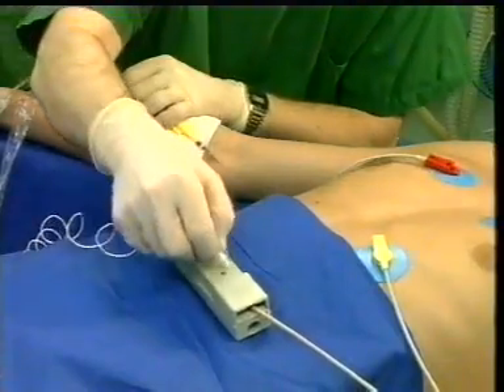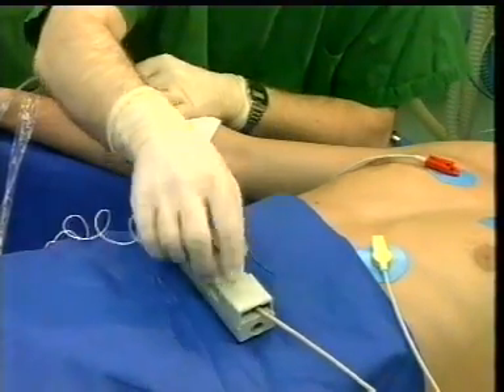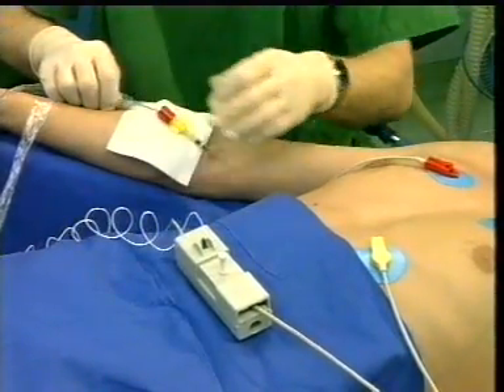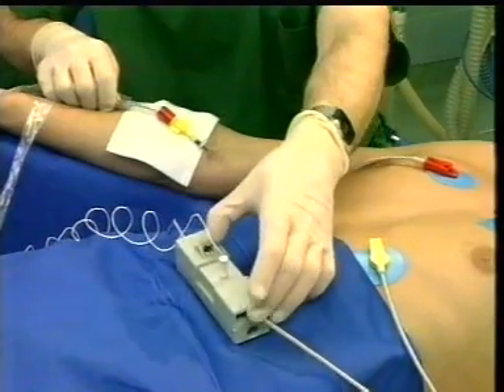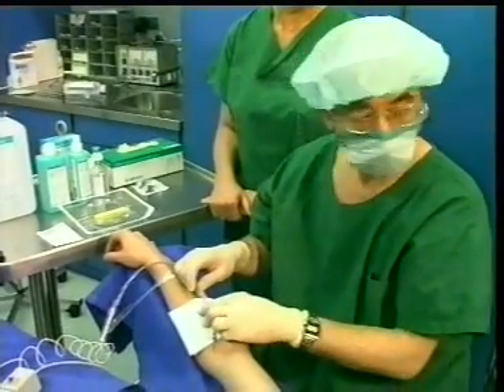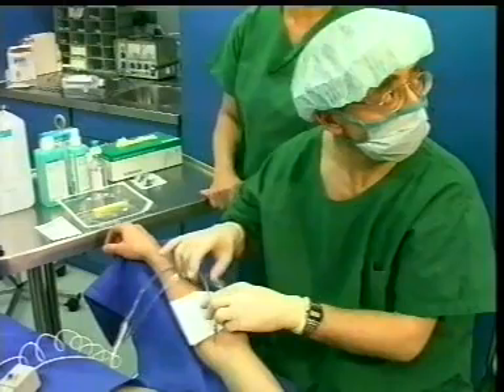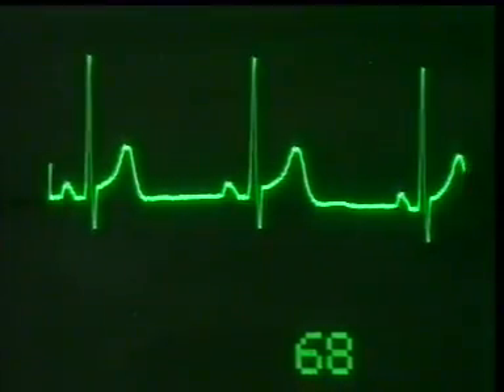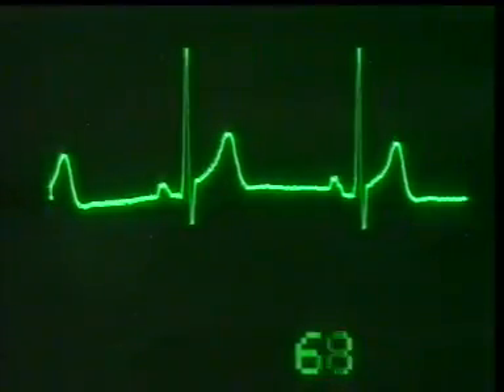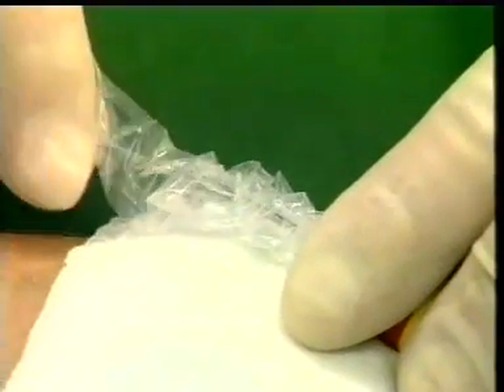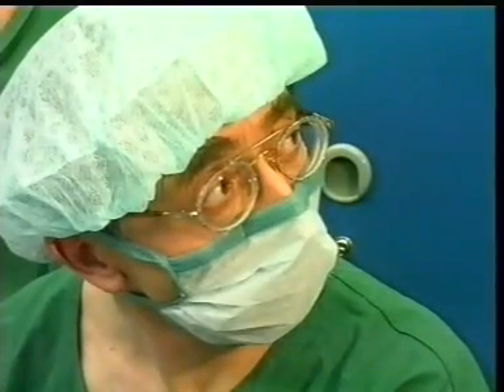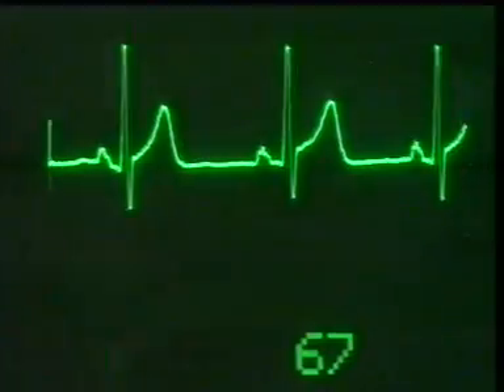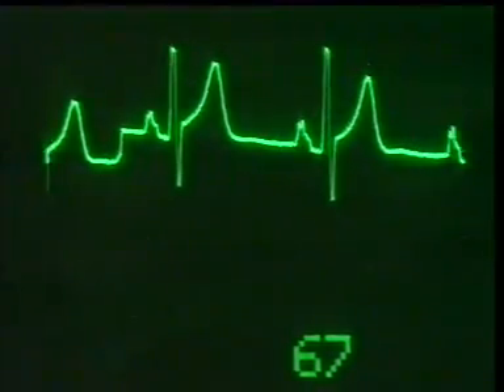The other end of the connection cable is inserted in the universal adapter. Then the ECG unit is switched over to intra-atrial monitoring. As the catheter is advanced, the physician watches the ECG monitor. To begin with, it shows a normal signal. However, when the catheter reaches the right atrium, the P wave of the ECG undergoes a marked change. This permits reliable monitoring of the location of the catheter tip.